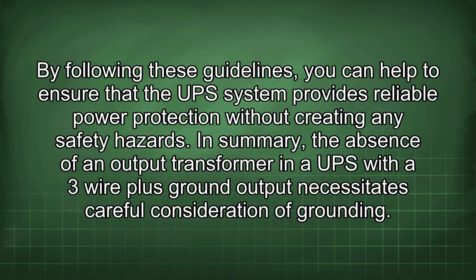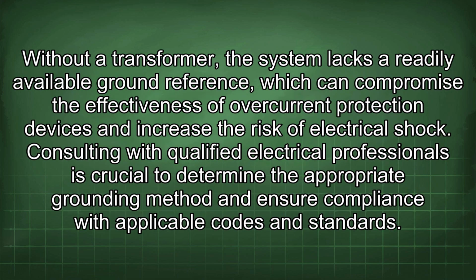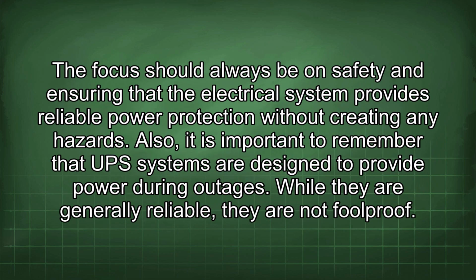safety hazards. In summary, the absence of an output transformer in a UPS with a 3-wire plus ground output necessitates careful consideration of grounding. Without a transformer, the system lacks a readily available ground reference, which can compromise the effectiveness of overcurrent protection devices and increase the risk of electrical shock. Consulting with qualified electrical professionals is crucial to determine the appropriate grounding method and ensure compliance with applicable codes and standards.